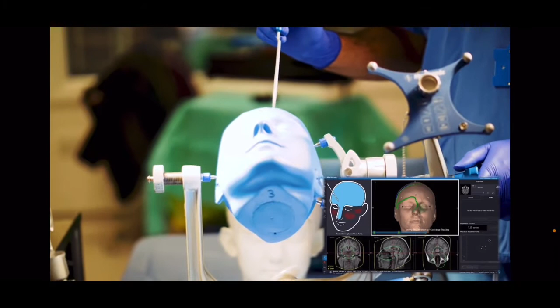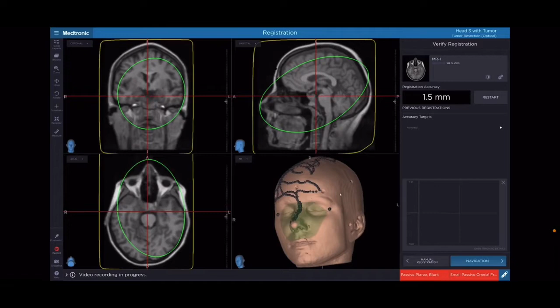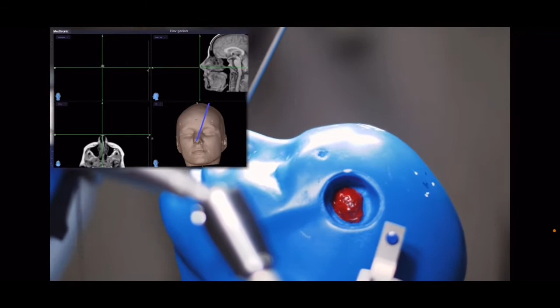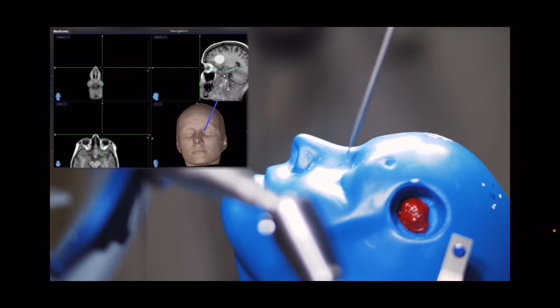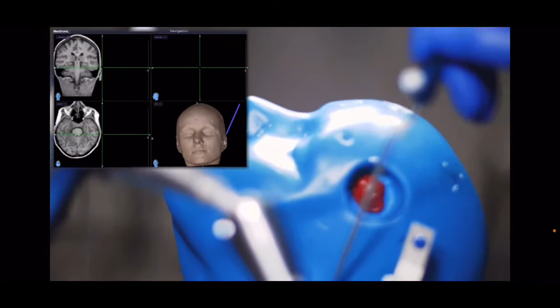We're going to be doing registration, as we mentioned before, marking out lots of points with the infrared pointer. Now, we can verify the registration. We've got 1.5mm accuracy, which will do for this simulation. So, we're going to touch the tip of the nose on the model, and you can see in the MRI that that correlates well. Let's look at the inner part of the eye, and that looks good, the outer part of the eye, and the tip of the ear. And this is all looking like it's corresponding really nicely.